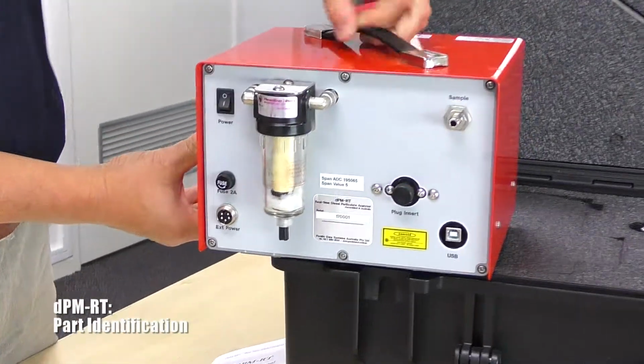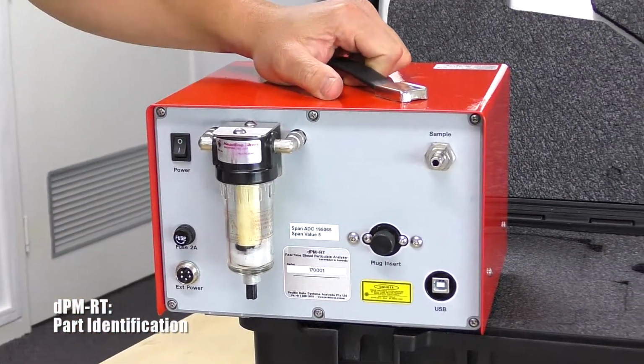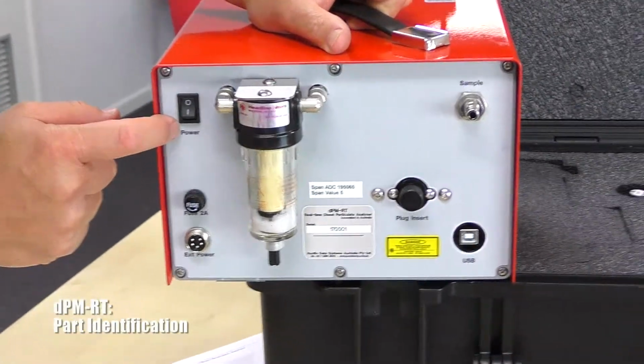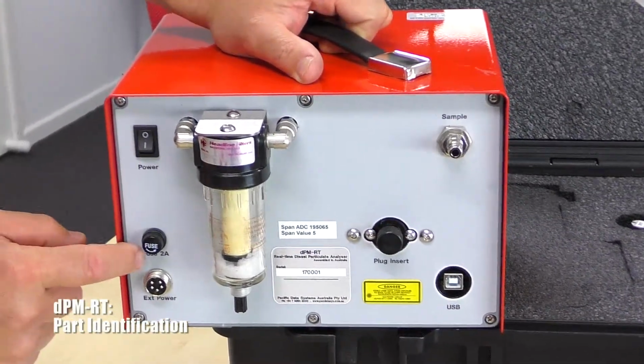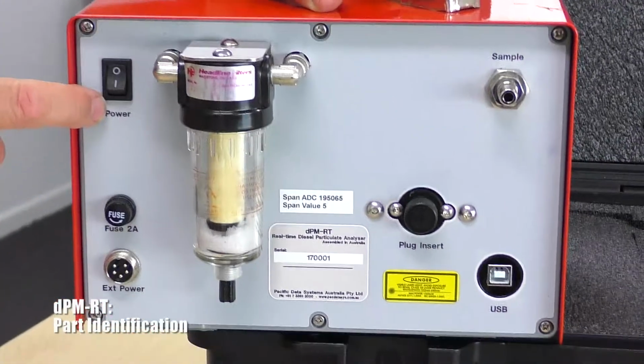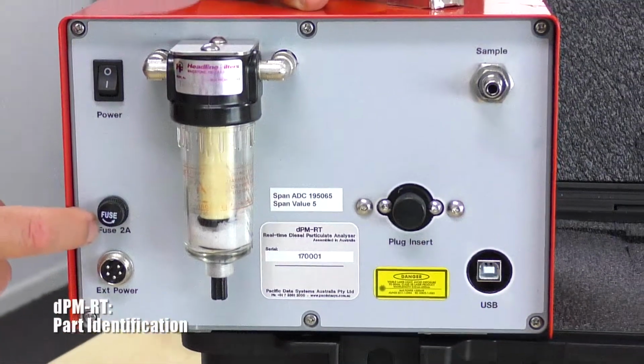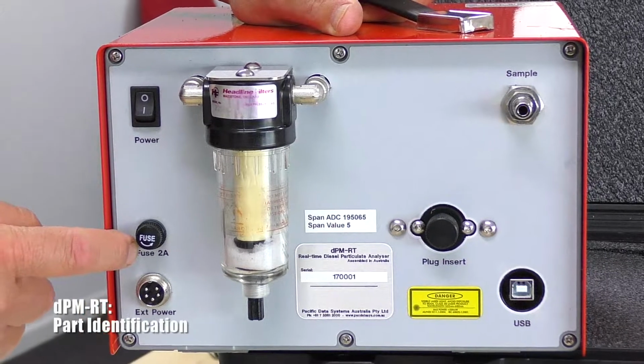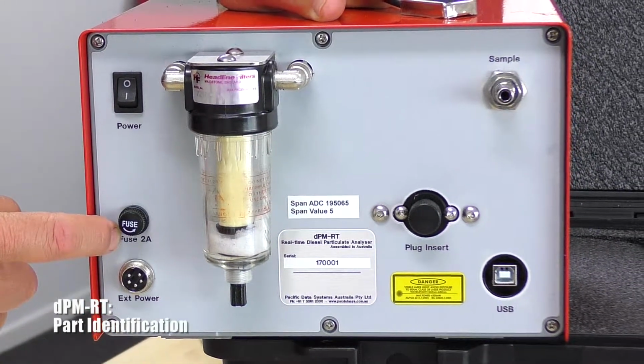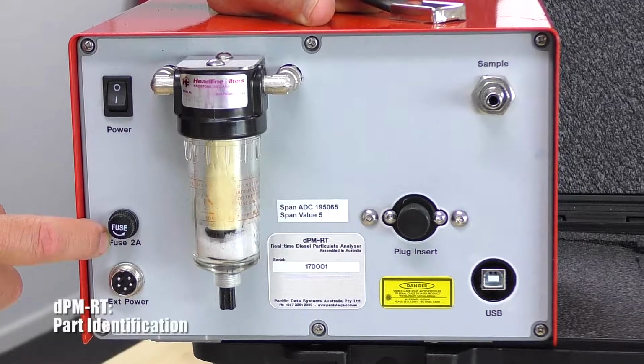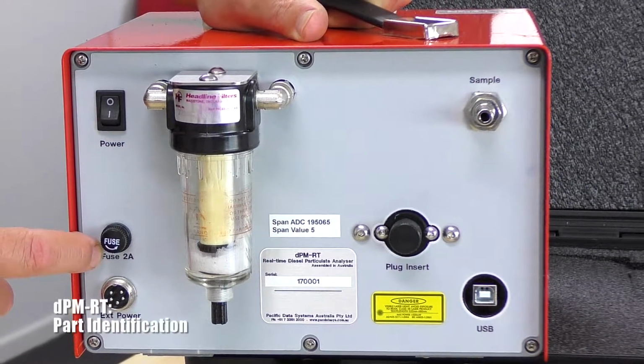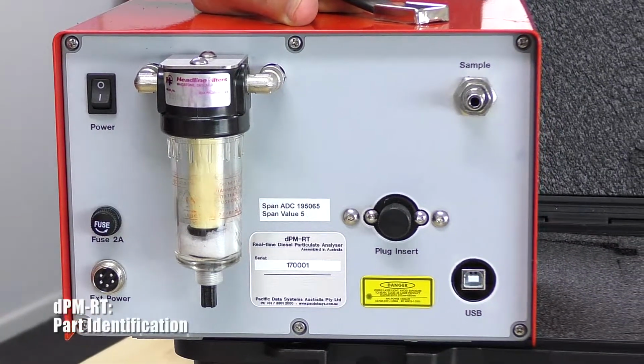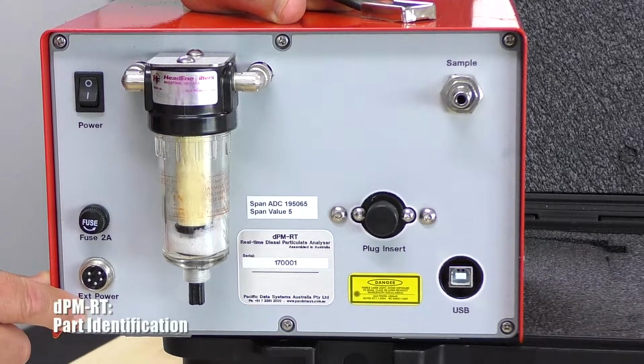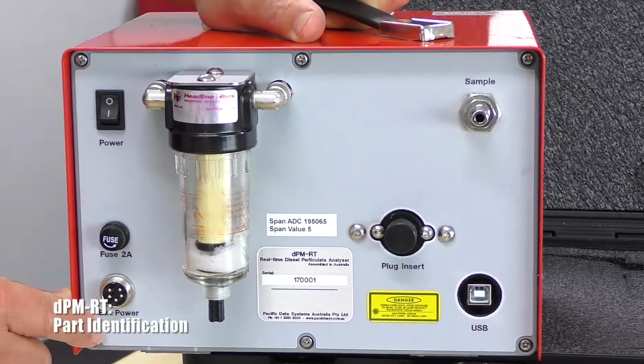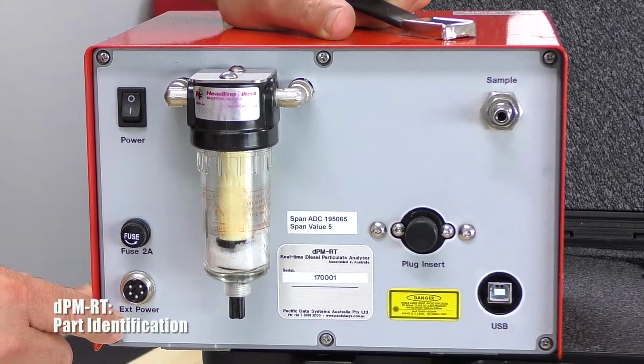I'm lifting the unit up by the carry handle, and on the back of the instrument on the top left hand side you have the power button, you have a fuse. So if the unit does not switch on, first port of call is to check if the fuse is blown, and the second port of call is to check that there's actually a charge in the internal battery. This is your external power connection for connecting the external power supply and battery charger.